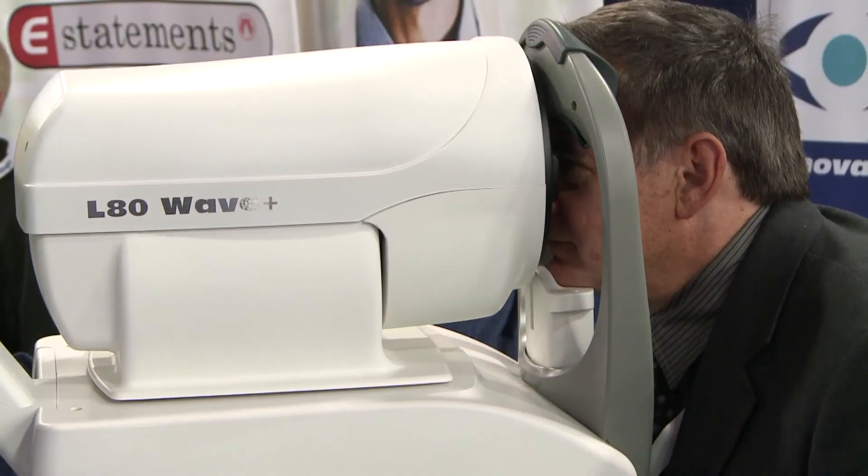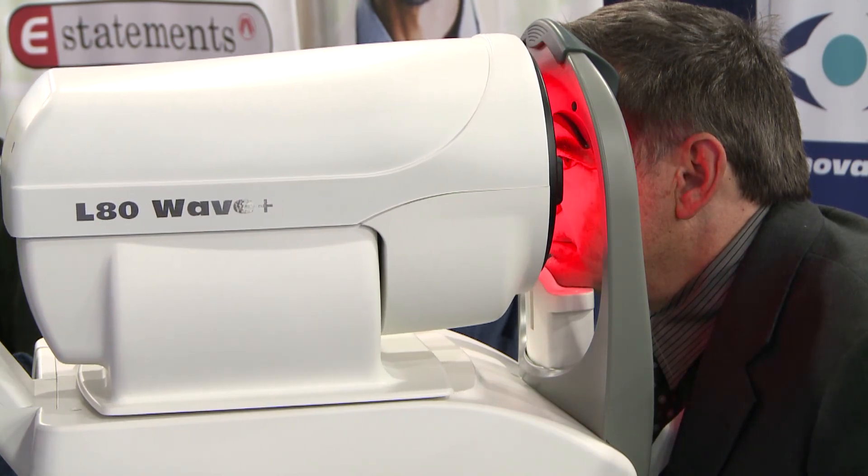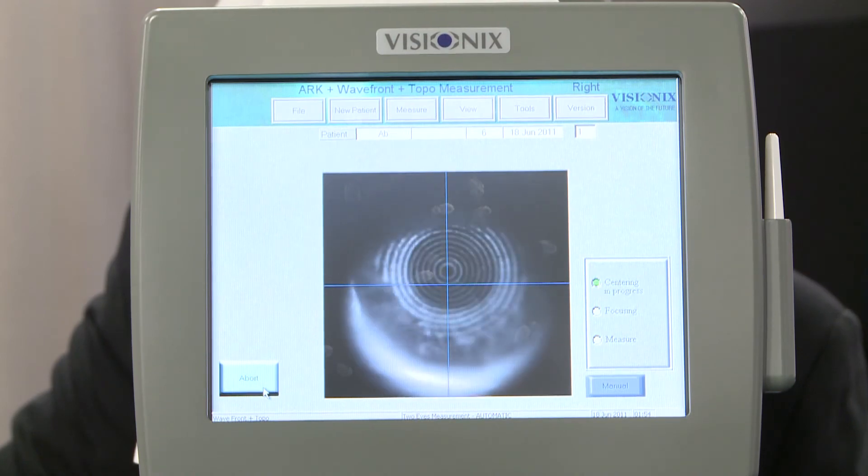The other brand under the Luneau Technology umbrella is Visionix, and Visionix' flagship product is the L80. The L80 is a wavefront aberrometer — it's a Hartmann-Shack based sensor, and it measures 3 and 5 millimeter, or day and night, ARK data, corneal topography, and wavefront aberrometry information.